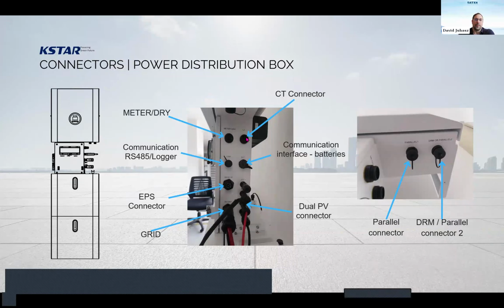So we can decide to use a standard meter if we want to check the cost fee, or we can use the cables with the CT that we give with the inverter as an extra accessory, if you are within 20 meters of the connection point. It has the communication interface with the batteries, and on the bottom of this inverter, on top of the distribution box, there is the parallel connection and the DRM parallel connection. The DRM is responsible for limiting the output of the inverter by dry contacts.